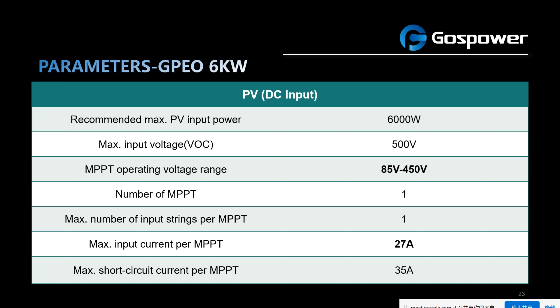Next page, let's discuss the parameters of this inverter. On the PV side, the recommended maximum PV input power is 6,000 watt, and the maximum open circuit input voltage is 500 volt. The MPPT operating voltage range is from 85 volt to 450 volt, and the number of MPPT is 1. The maximum input current per MPPT is 27 amps, which means you can have 2 strings of solar panels in parallel connection. The maximum short circuit current per MPPT is 35 amps.